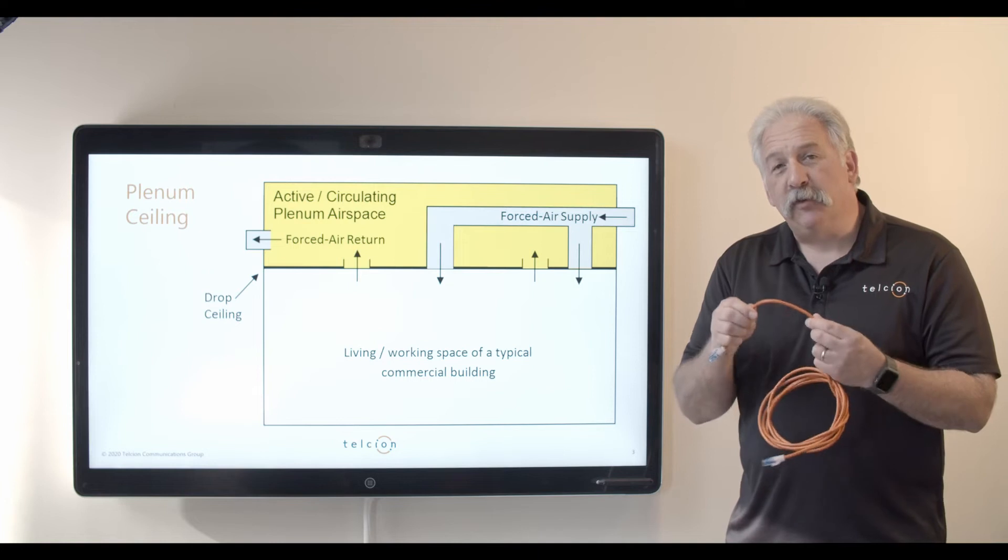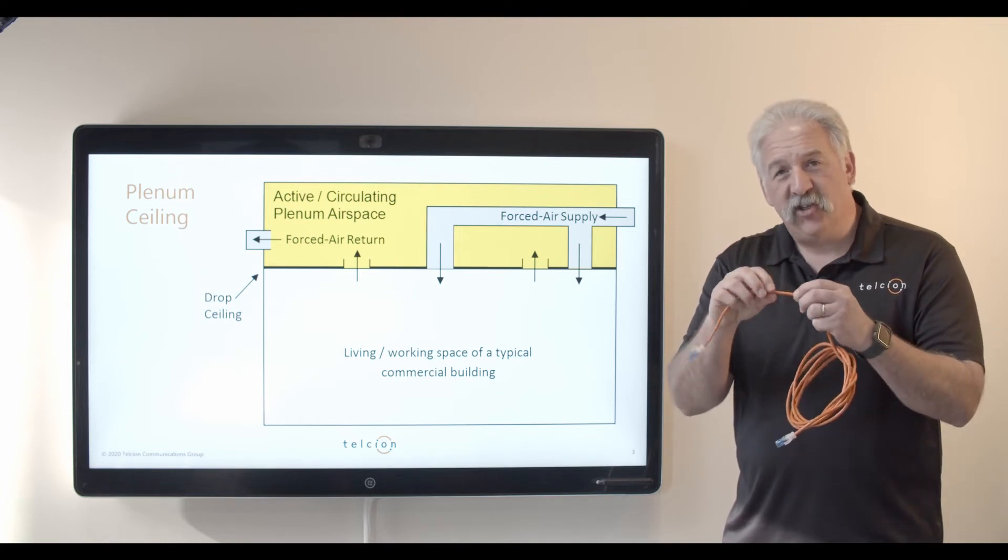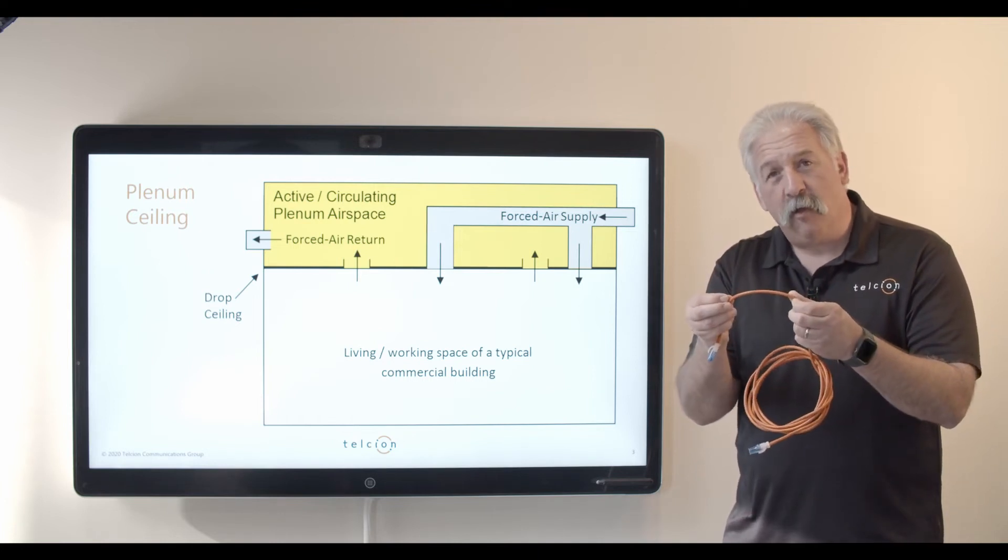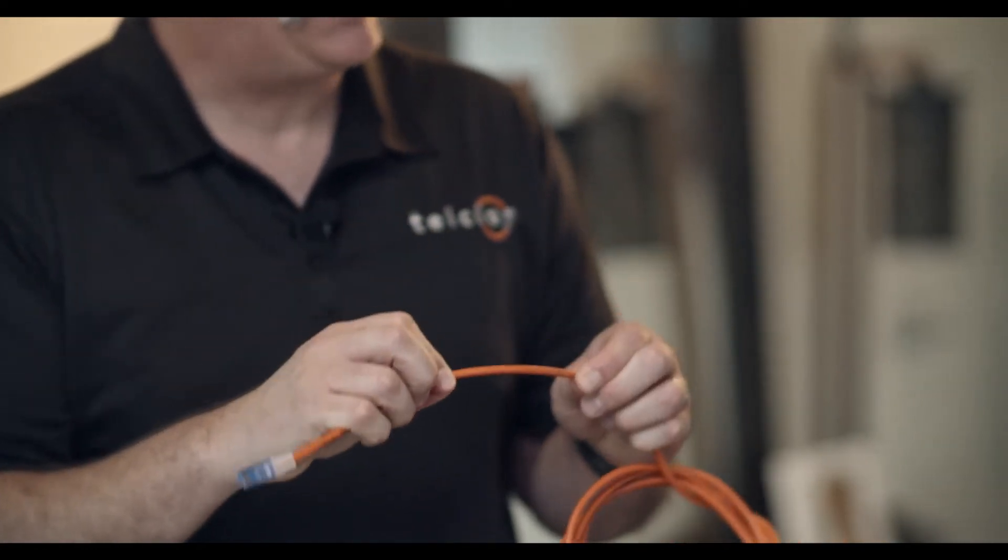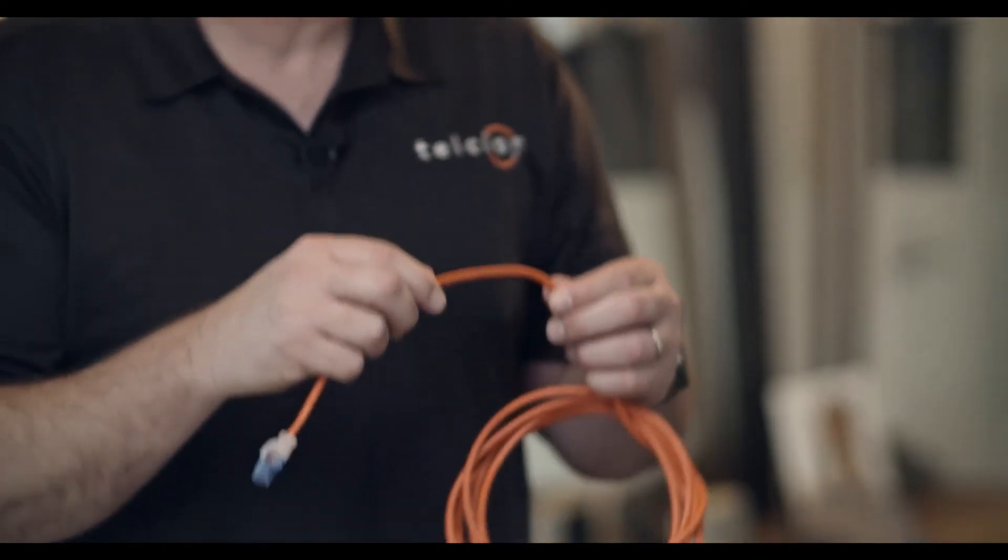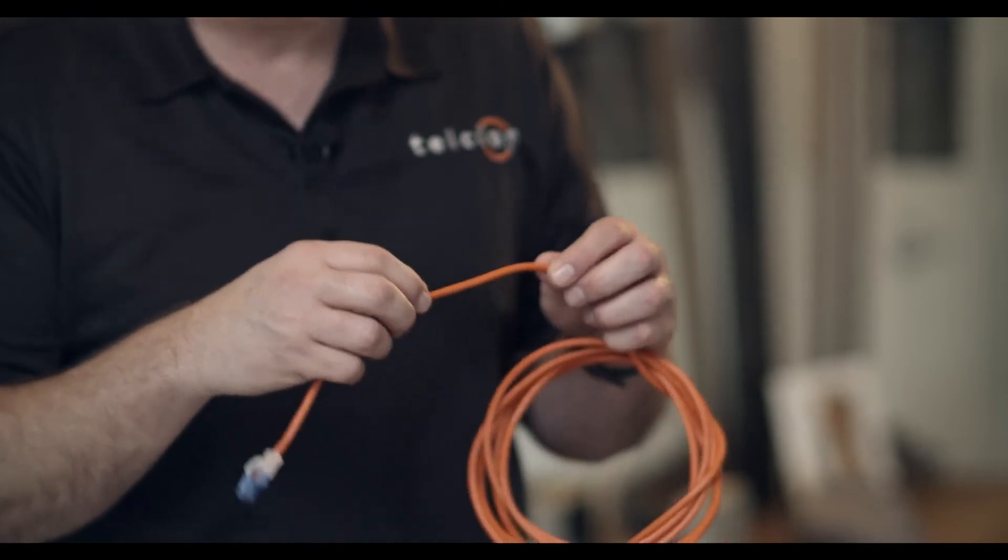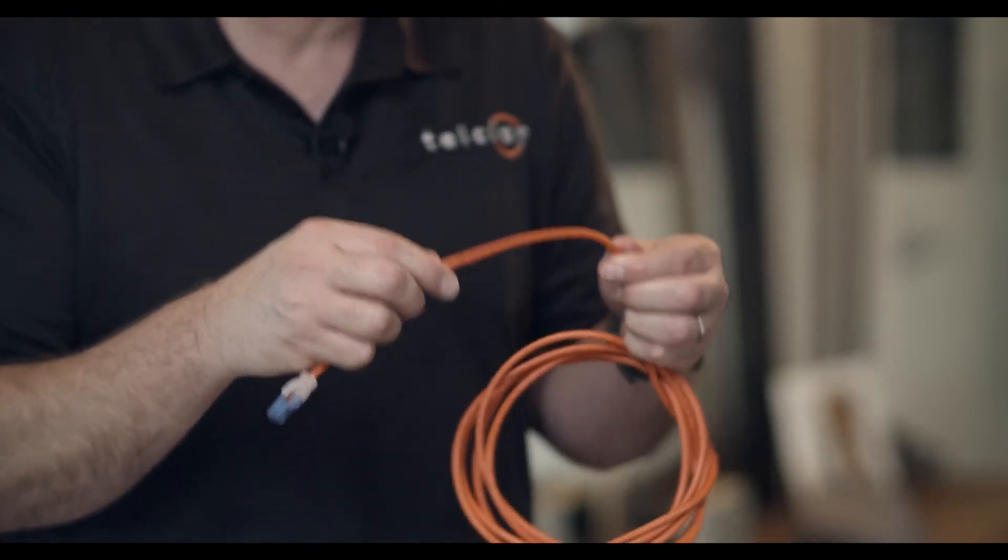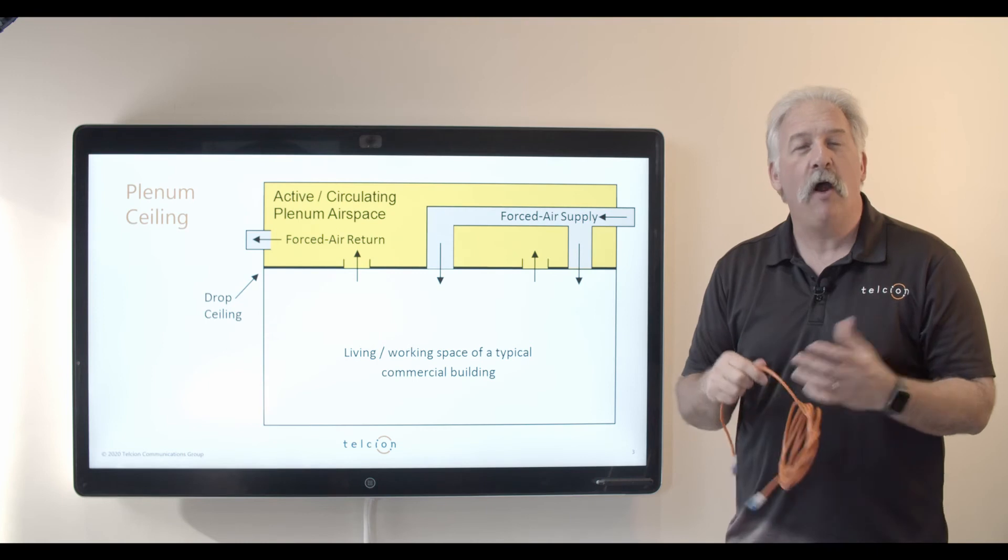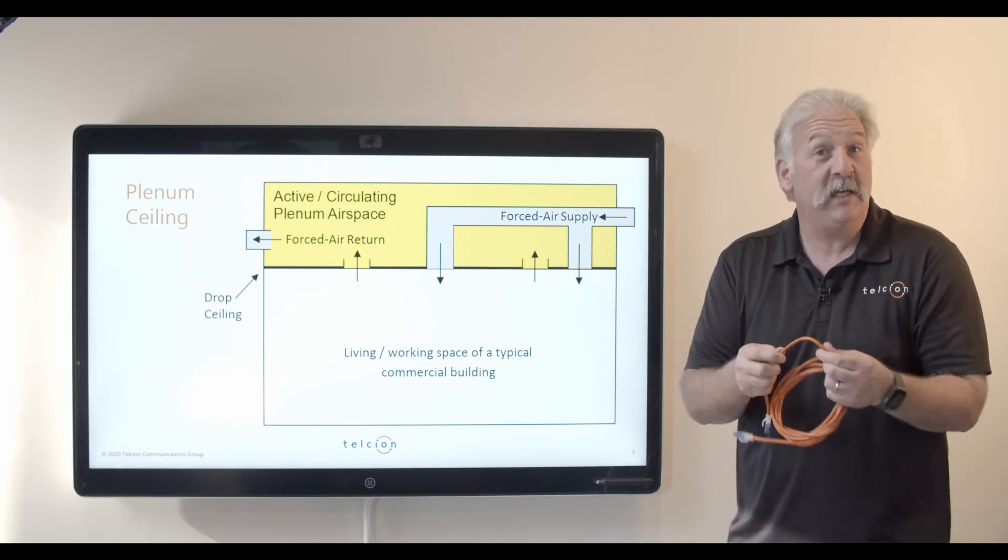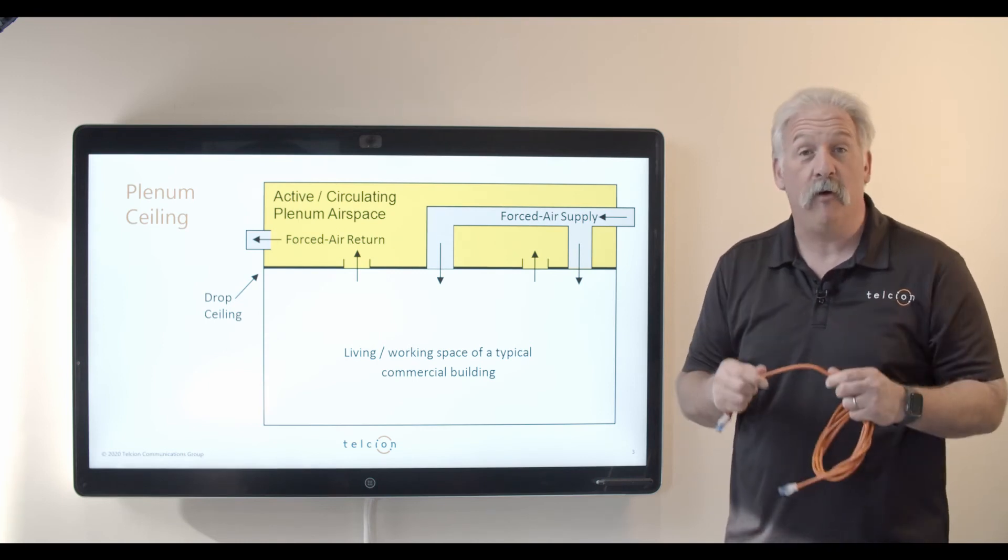The main difference between plenum and non-plenum cabling is the sheath that goes around the cable itself. The plenum cabling has been manufactured to handle higher temperatures and has a different kind of smoke toxicity that goes with it and as a result it costs about twice as much as non-plenum cable does. Really why the question comes up so often is do we need it or do we not need it because of the cost that's involved.